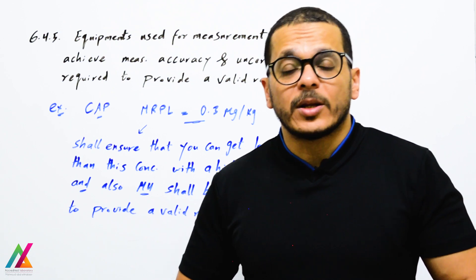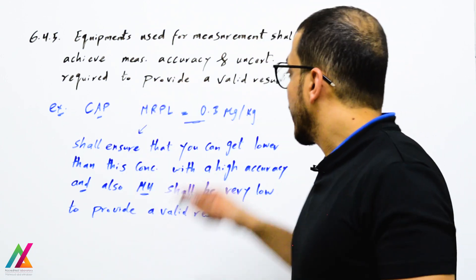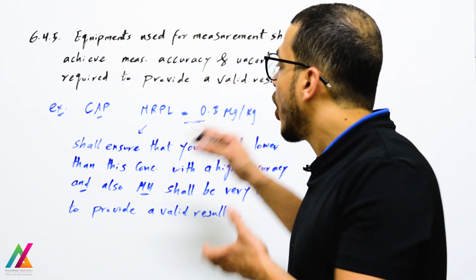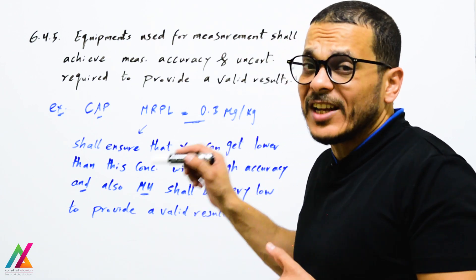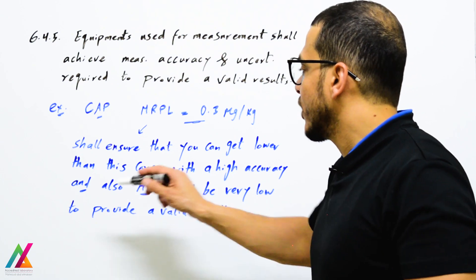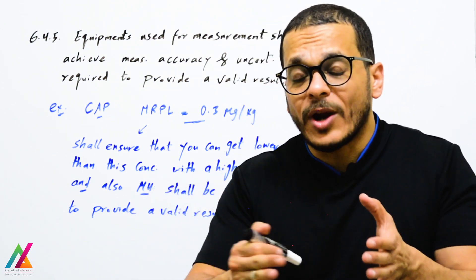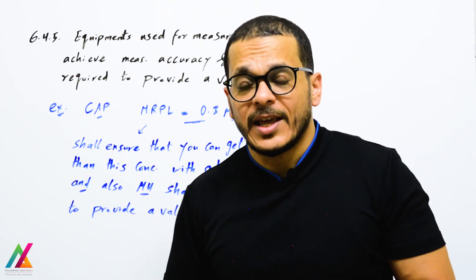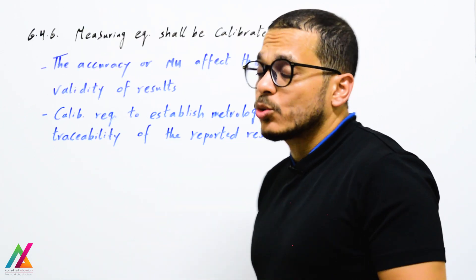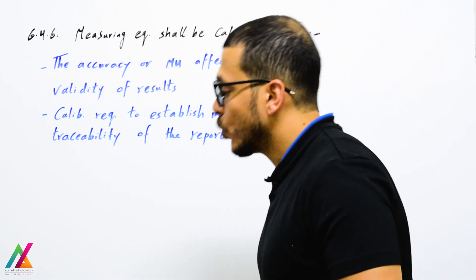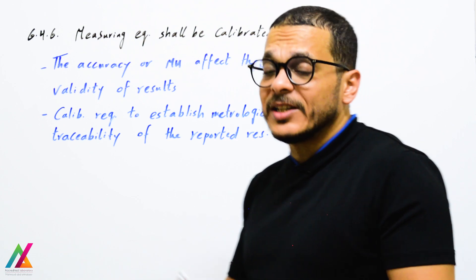You shall ensure the instrument can cover the working range from the lowest to the highest concentration for target analytes with high accuracy, and that it achieves the required uncertainty. This is confirmed during method validation when evaluating method performance parameters. As an example, chloramphenicol in food of animal origin is a carcinogenic and banned compound. The minimum required performance limit (MRPL) is 0.3 µg/kg according to European limits — this is the highest accepted concentration. The instrument must detect below this concentration with high accuracy and sufficiently low measurement uncertainty.